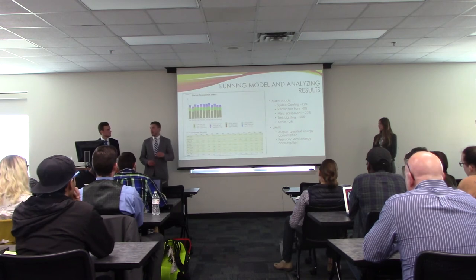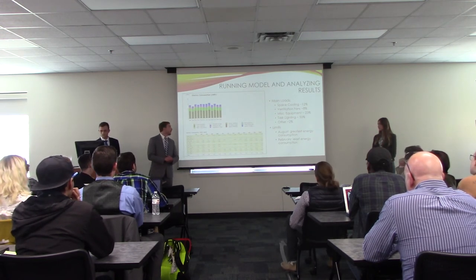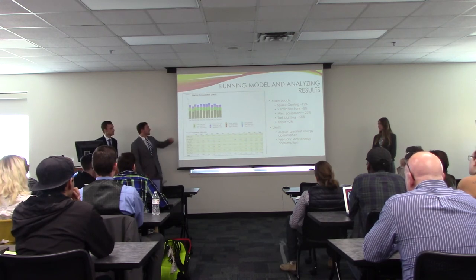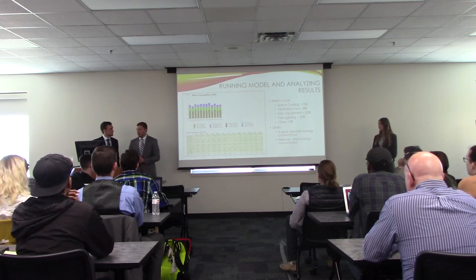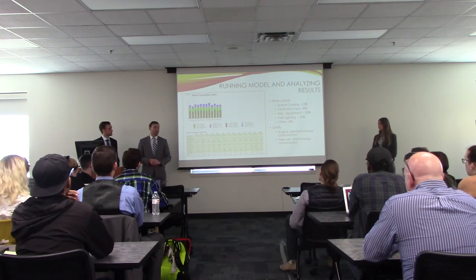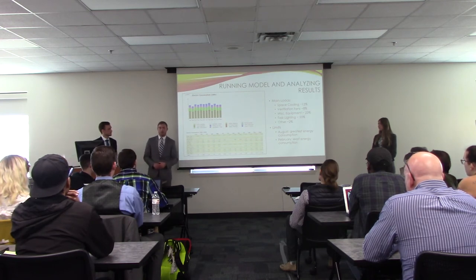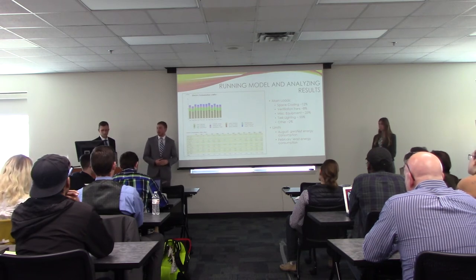Once we input all values into the system, we got this report. Task lighting and miscellaneous loads account for about 80% of our data — quite high loads, but they stay standard throughout the entire year. Another thing to note is that our cooling exceeds our heating even in the winter months, which was a problem we knew we would have to address.